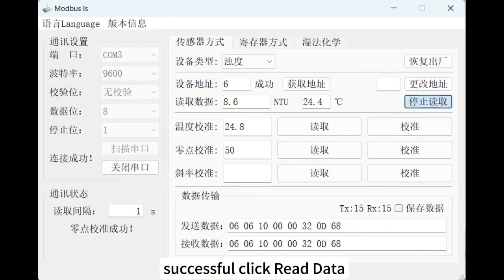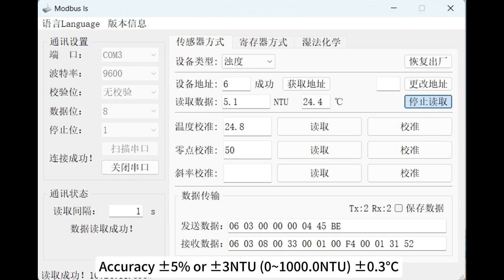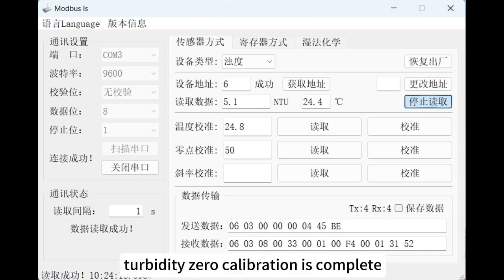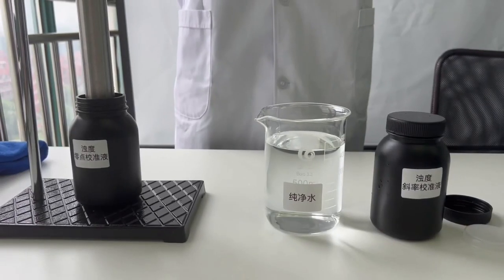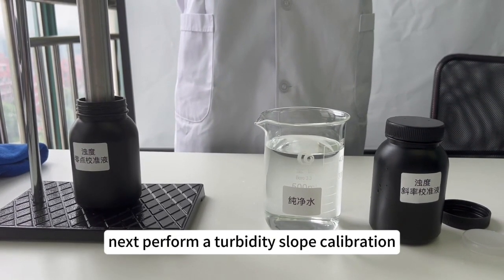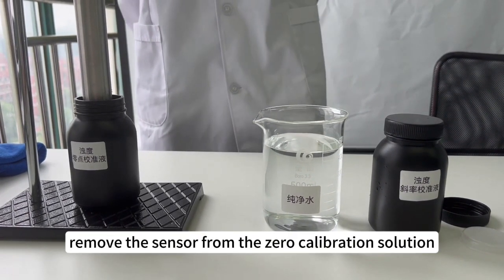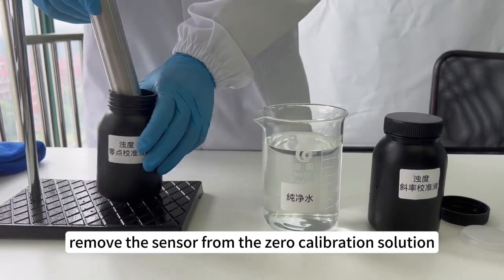Click Read Data. Turbidity Zero calibration is complete. Next, perform a turbidity slope calibration. Remove the sensor from the zero calibration solution.